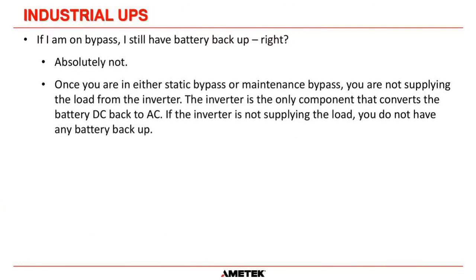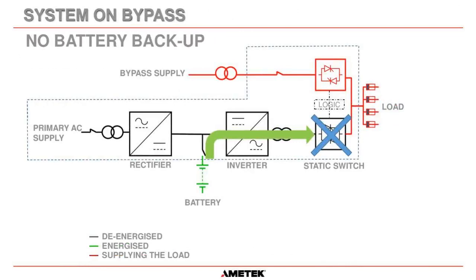One more misconception: 'If I'm on bypass, I still have battery backup, right?' Absolutely not. Once you are on static bypass or maintenance bypass, you are not supplying load from the inverter. Whenever you are not supplying power from the inverter, you are not connected to the battery — only the inverter converts DC back to AC. So if the inverter is not supplying the load, you do not have any battery backup. If bypass fails while you're on bypass, unfortunately you will lose power to the load because the battery cannot supply the inverter through the inverter static switch, since it is off.